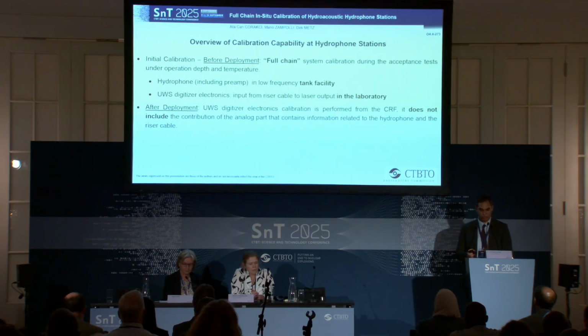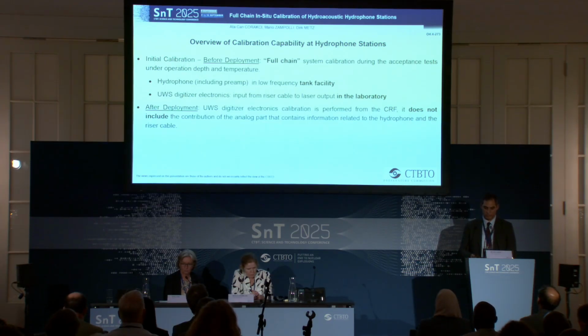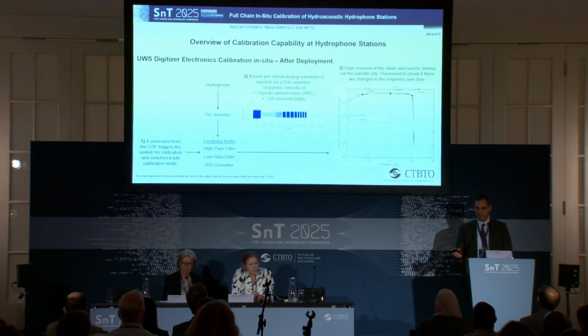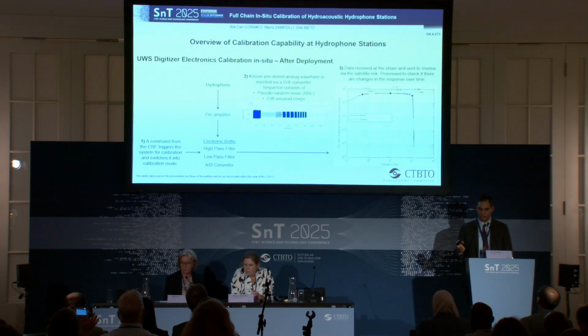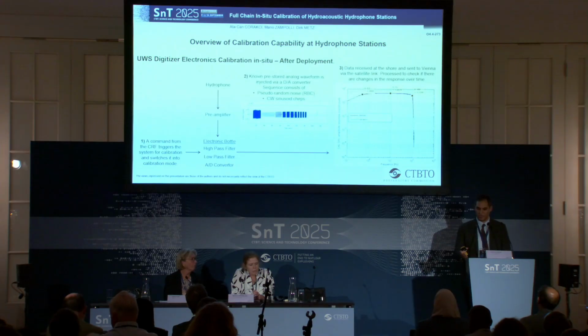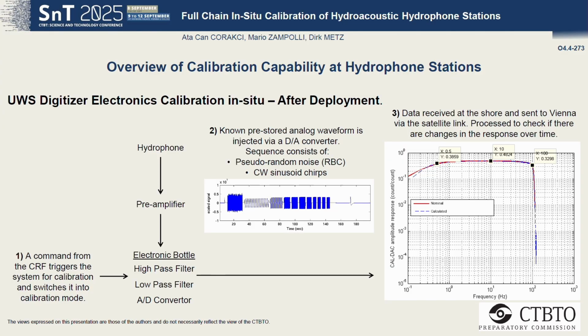That means that the contribution of the analog part is not considered in the calibration. And this analog part contains the hydrophone, the riser cable, and the preamplifier, which is very critical from our perspective. And this is how the calibration is done after the deployment. From the CRF, a signal is sent to the electronic bottle, a different type of signals, a continuous signal that we trigger from the CRF, and the electronic response is captured and compared with the nominal response of the system that was initially calibrated during the factory acceptance test. So you see in here, the hydrophone and the preamplifier are not considered in this chain.